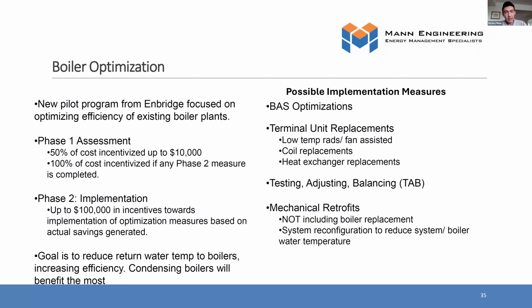And testing, adjusting, balancing. So TAB, it's something that's very much overlooked in a lot of buildings. But to give an example, I've seen lots of buildings where there may be a few suites in the building, or maybe one riser that is consistently always much colder than the rest of the building. And so they call the BAS guy and say, hey, we need the boiler plant temperatures increased. So they'll go ahead, and the whole heating curve will be adjusted to provide enough heat to that one suite or that one riser.